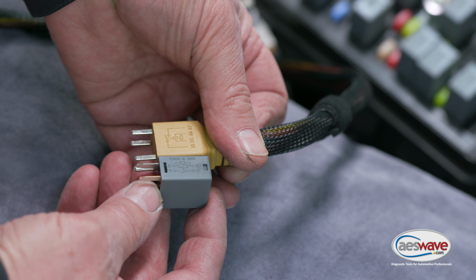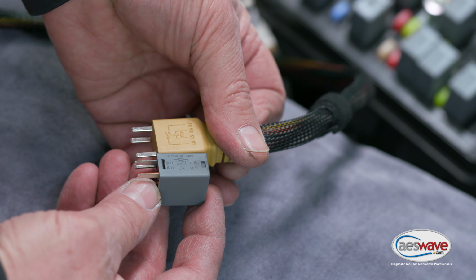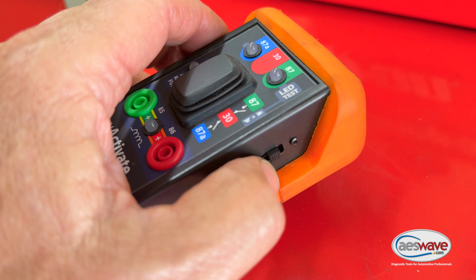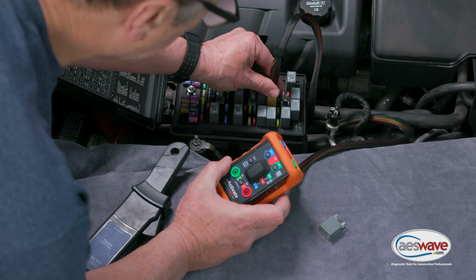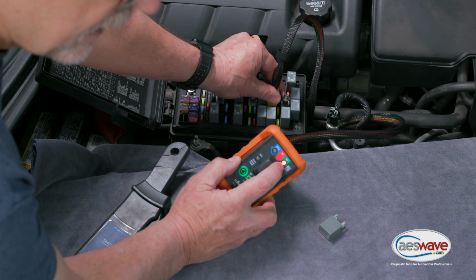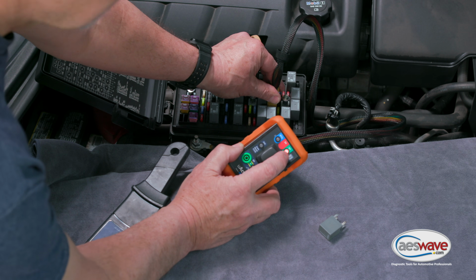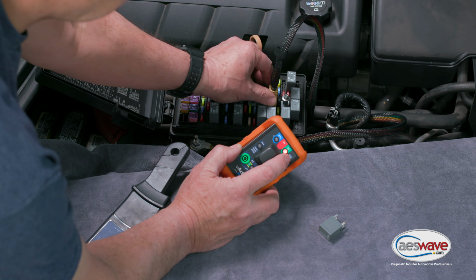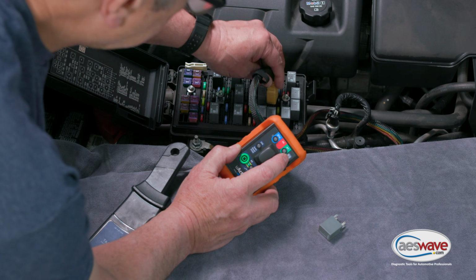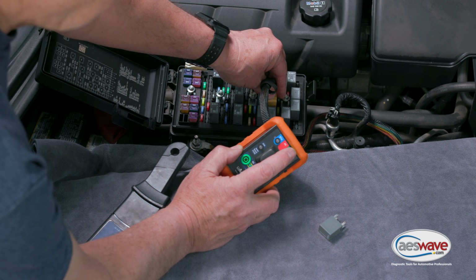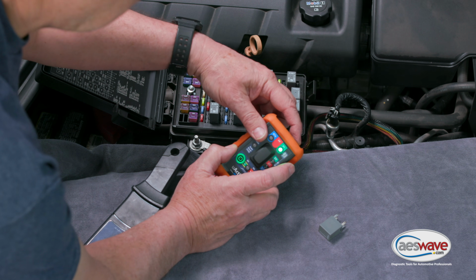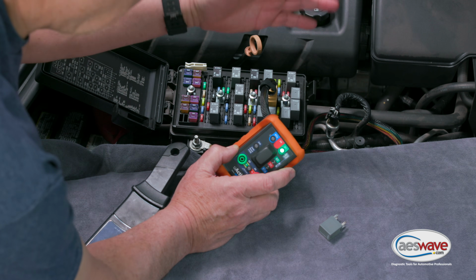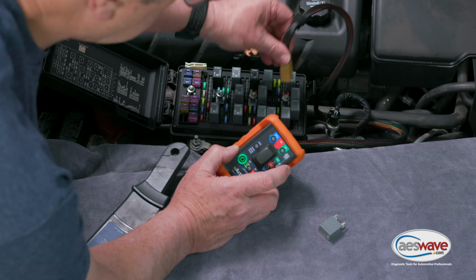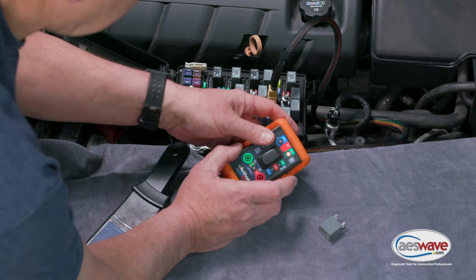In a previous video, we talked about how to verify the correct polarity here. We would just turn on our LED switch and plug that in. If we have that in the red, 87 shows red, that means we've got it set up properly. If we have it flipped around this way, then 87 is actually the hot lead, and that might mess you up on testing. So it's always a good idea to get it in the proper orientation.